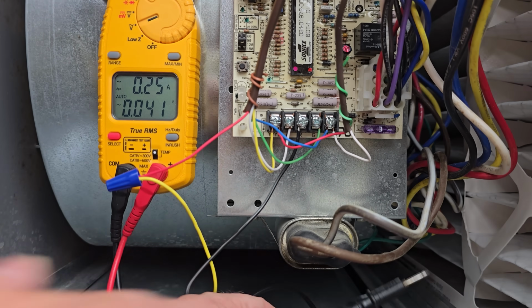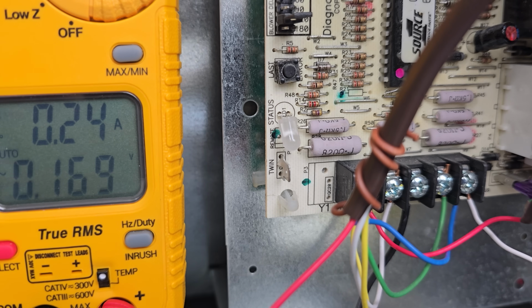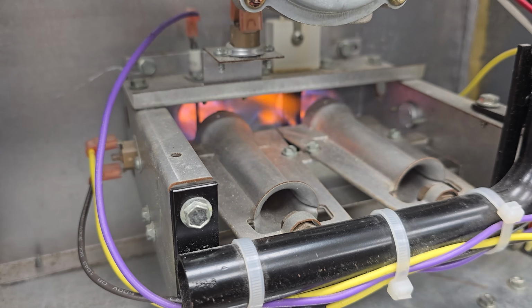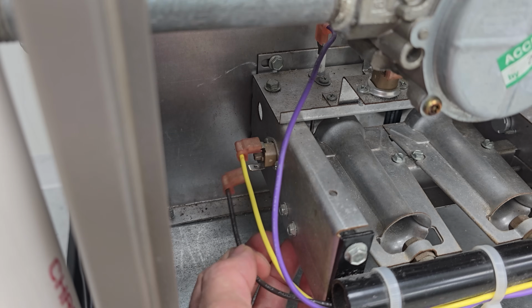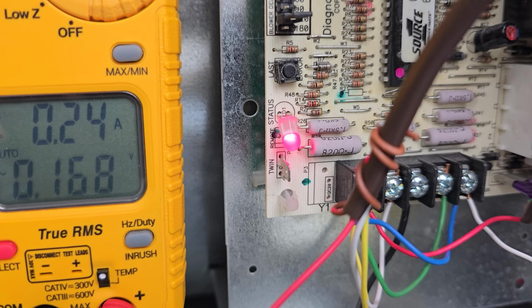I'll give you an instance of what that looks like. That right there is the flame rollout switch. And that is a very important safety switch. It protects against potentially flames popping out from that combustion chamber. And so what's happened now is you have the blower motor running and the inducer motor running, and it's not going to allow ignition to occur even if there is a signal for heat to turn on. Now we're going to move on to another scenario.